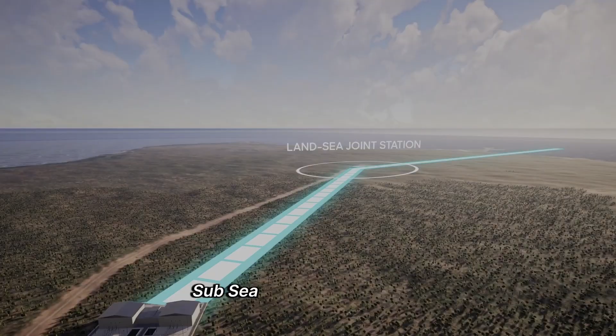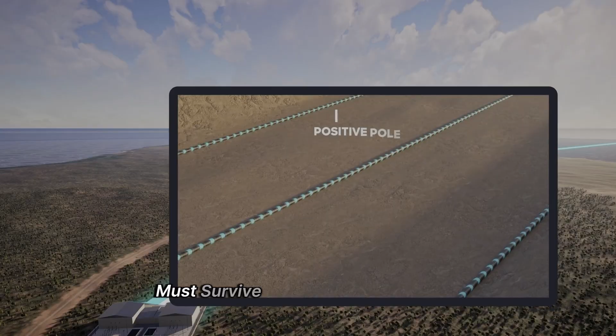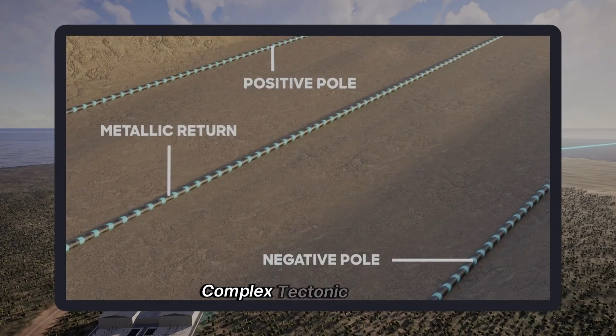Transporting power across continents requires high-voltage direct current, HVDC, technology to minimize transmission losses. The Singapore Link will be the world's longest subsea cable system, utilizing a bipole configuration at a staggering plus or minus 525 kilovolts. The engineering feat lies in the 4,300-kilometer subsea route. These cables, roughly 170 millimeters in diameter, must survive depths of 2,000 meters and navigate the Indonesian throughflow's complex tectonic activity. Engineers use armored protection and seabed burial to mitigate thermal stress and physical damage from maritime traffic.